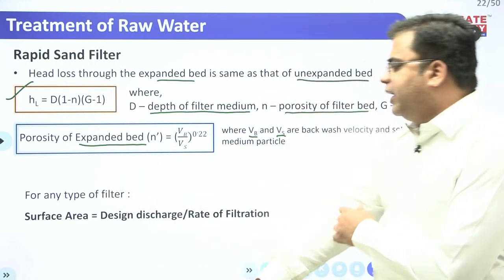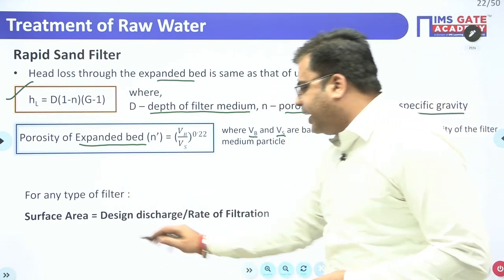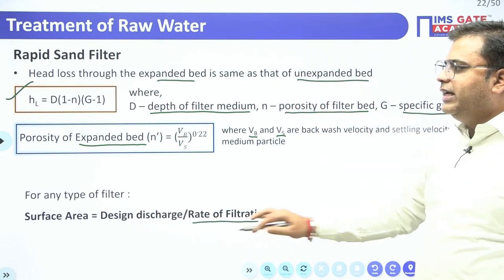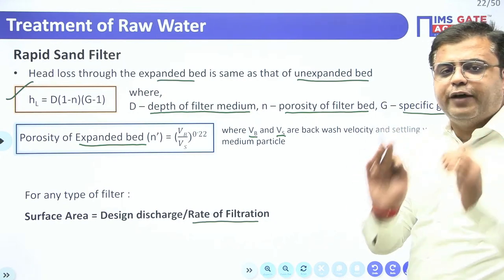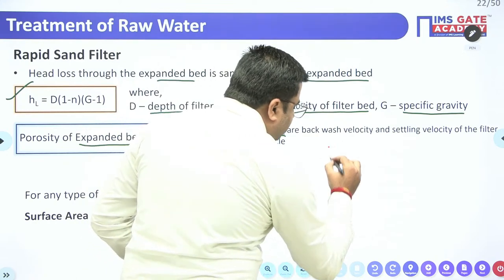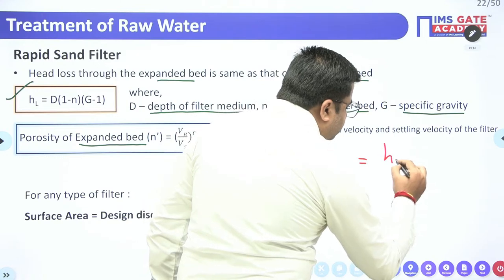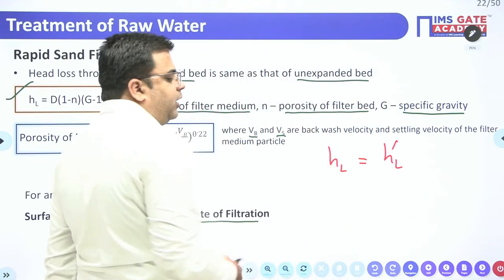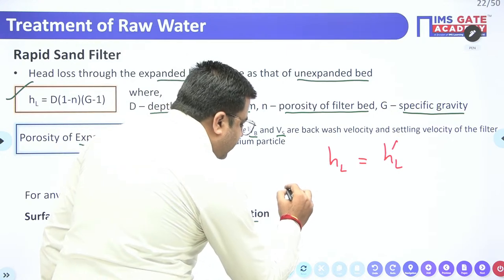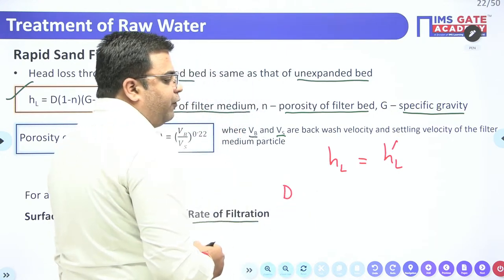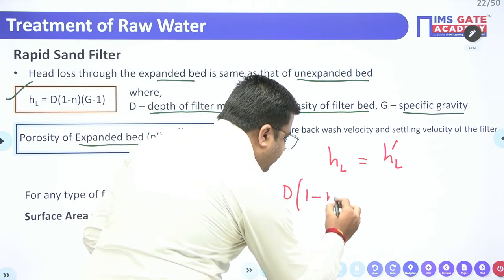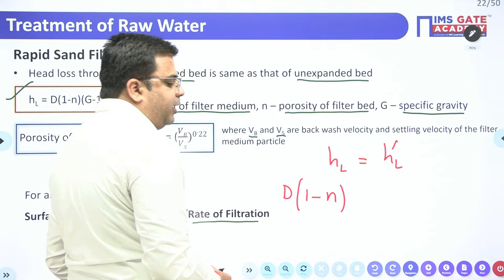So for any filter, surface area can be calculated as design discharge divided by the rate of filtration. All these three expressions are very, very important, right? Let me write down one more expression. I have told you that head loss through the unexpanded bed is equal to the head loss through the expanded bed, right?